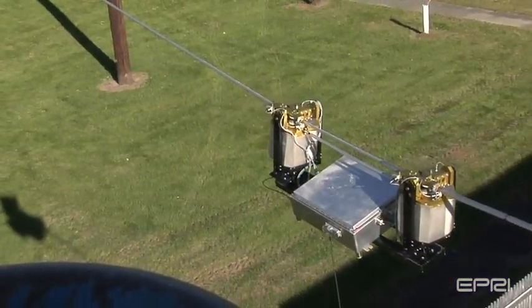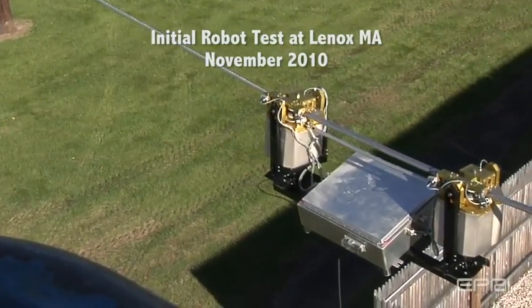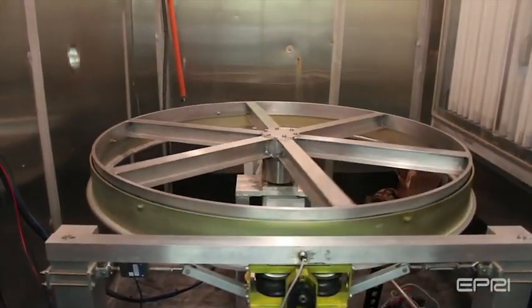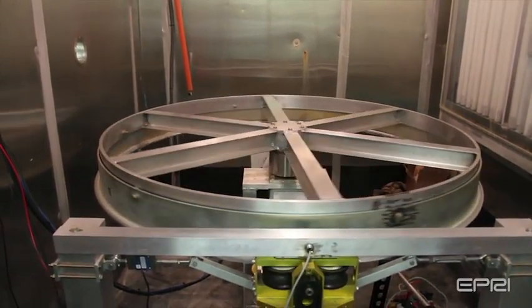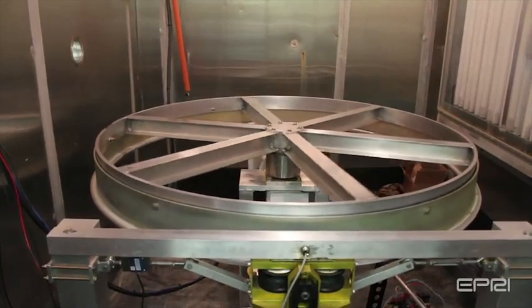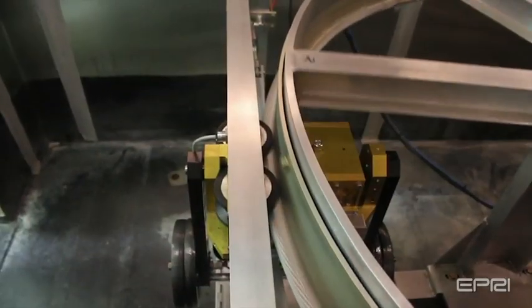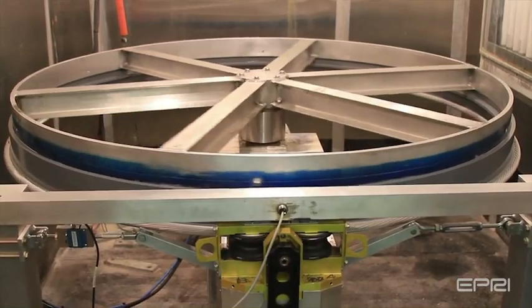The initial testing of the robot on the Lenox test loop revealed issues with the wheel design and the rapid degradation of its rubber compounds. A rotating wheel tester was constructed specifically to evaluate the performance of different proposed wheel design improvements in rubber compounds. The rotating wheel tester, dubbed the Wheel of Fortune, allowed the developers to accelerate the distances traveled by the wheel system on a transmission line simulator, and resulted in a successful wheel design using new material that was able to survive 2,000 miles on the simulator.